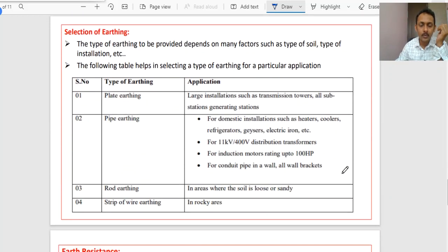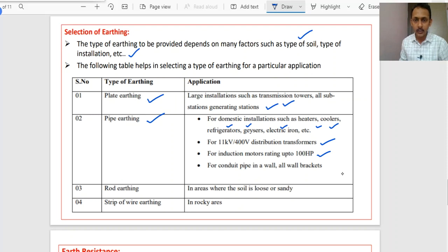Now coming to its selection, how the selection of earthing will be made depends upon many factors such as the type of the soil and the type of the installation, right? For example, plate earthing will be preferred for large installations such as transmission towers, substations and generating stations. At all those points you are going to go for plate earthing. For domestic installations such as heaters, coolers, refrigerators, geysers or electric iron boxes, we can go for the pipe earthing system. For 11 kV by 400 volts distribution transformers also, we can go for the pipe earthing system. For induction motors rated up to 100 HP, this can be preferred.